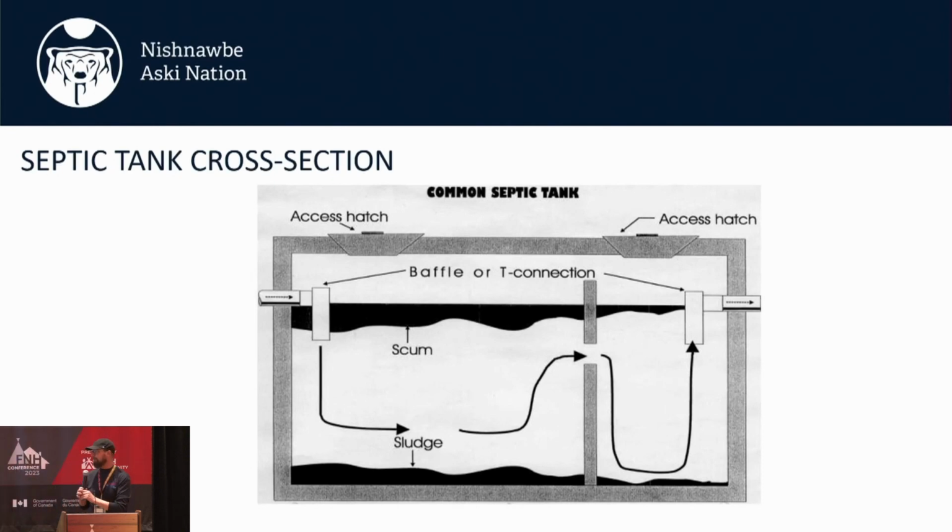You can see a lot of corrosion, particularly in concrete tanks. I know that most places are switching to PVC plastic tanks. At least in the NAN communities I work with, getting a concrete tank into the community is probably not a feasible thing unless you have road access. So PVC is pretty much common, but I've also seen a lot of PVC tank partition walls that don't exist, that break down, that aren't attached properly and are leaning over in the tank.